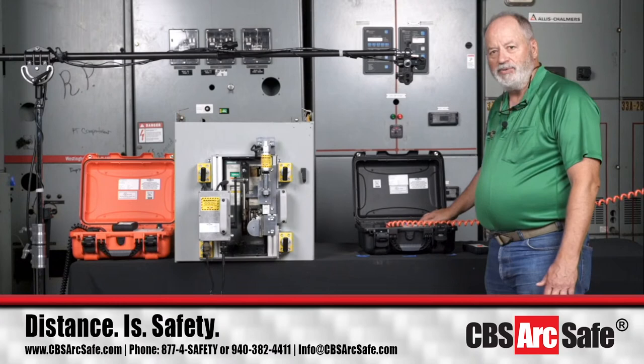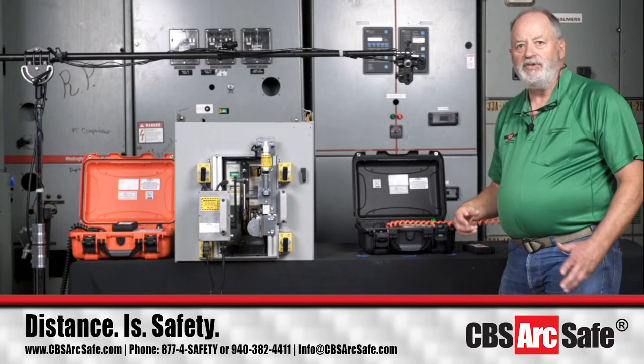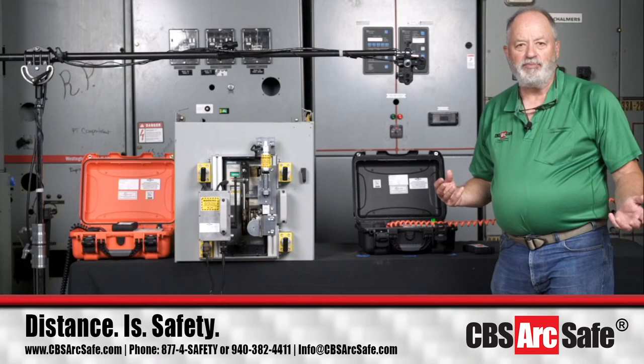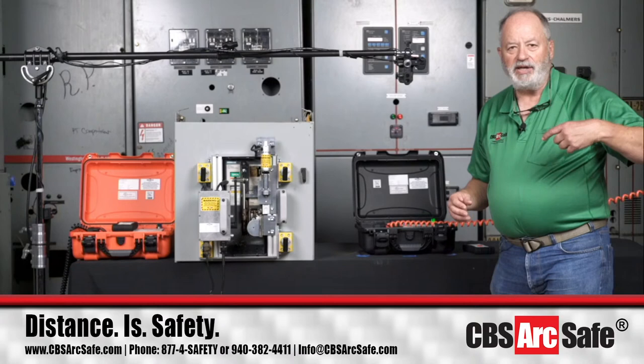So again, it depends upon your breaker type, and the information is going to be in the manual for the specific breaker type and which AR function you may or may not need, if you have anything. So things like a Masterpact breaker where you have a push button you've got to push in between beginning the racking process and when you get it to test, and you've got to push it again to be able to get it to disconnect.